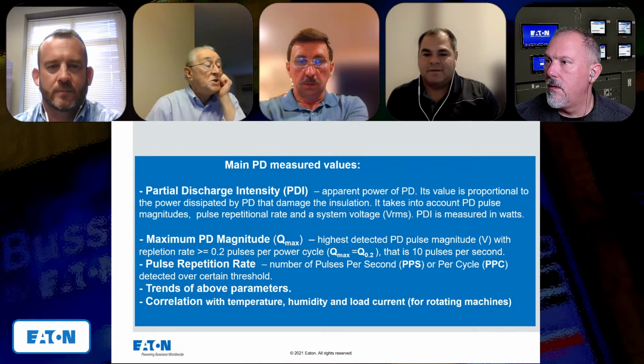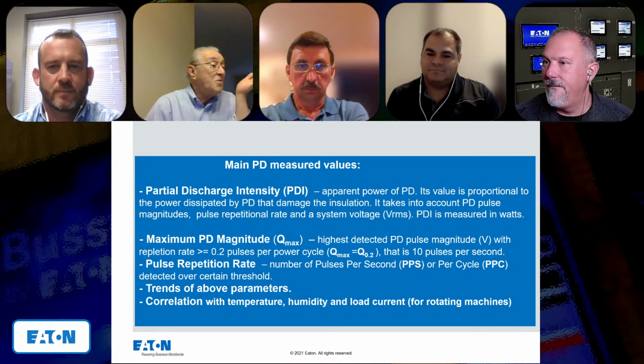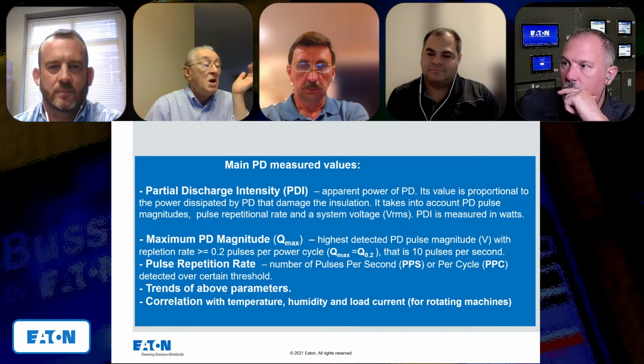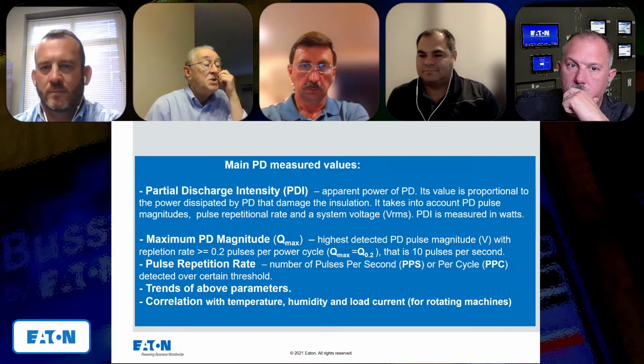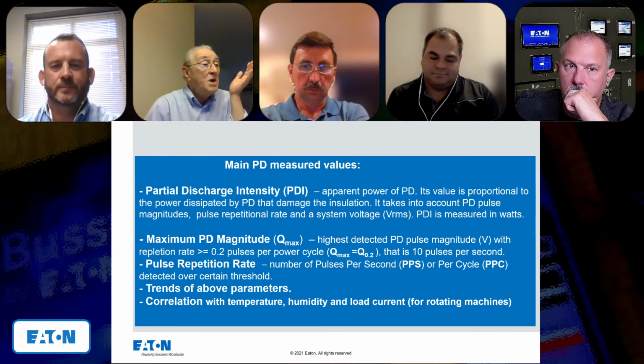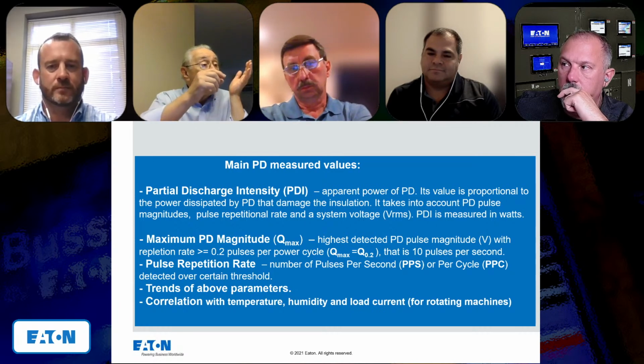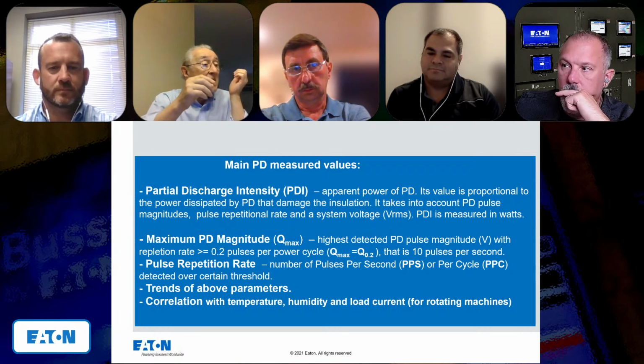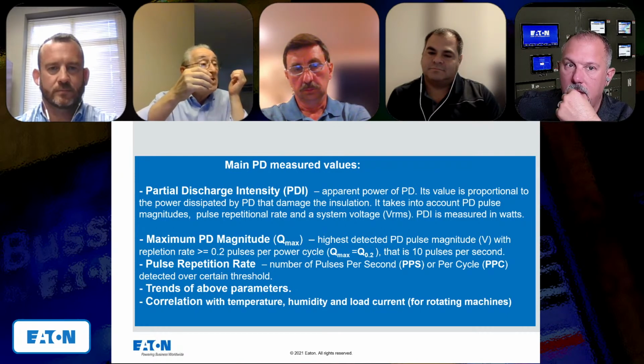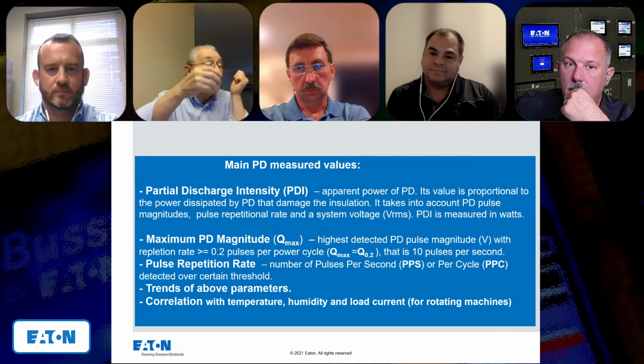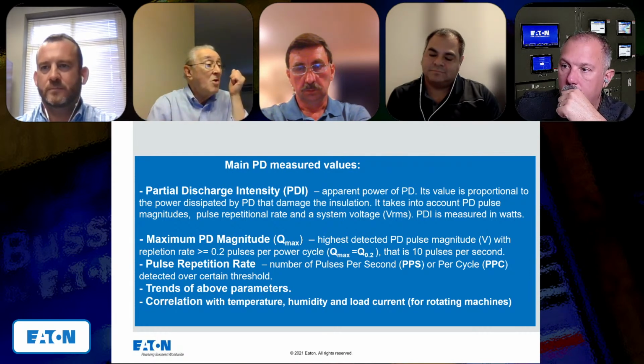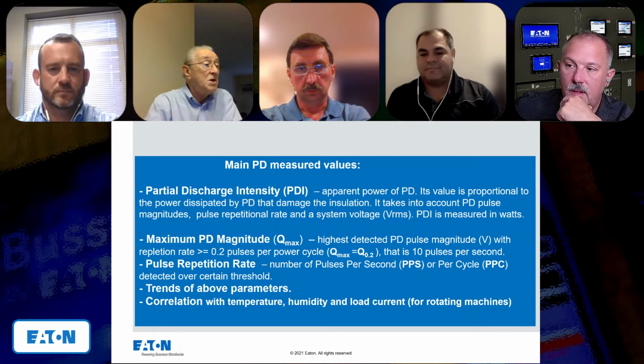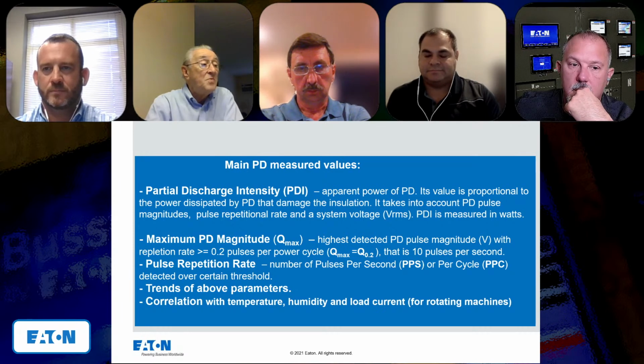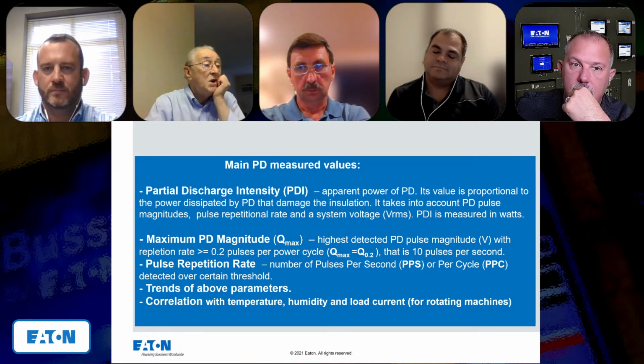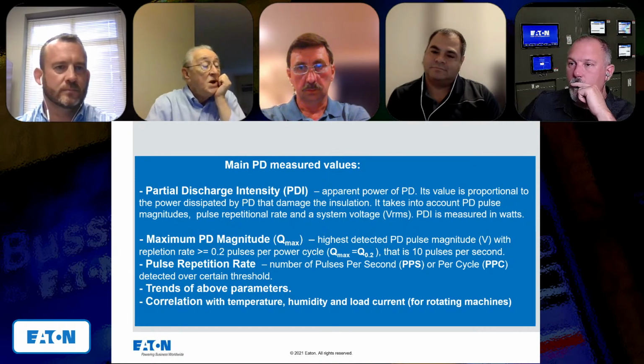These are the main partial discharge measurement values. First of them, you can see partial discharge intensity. It is the apparent power of partial discharge. Why apparent? Because nobody can measure the power of the spark inside the void. But you can measure the pulse, which appears together with the power voltage. So the partial discharge intensity is proportional to the power dissipation by partial discharge, which destroys insulation.